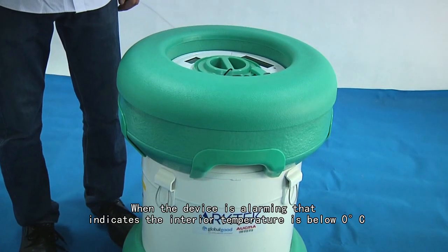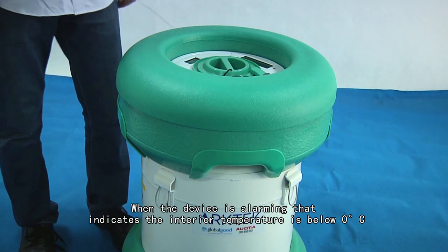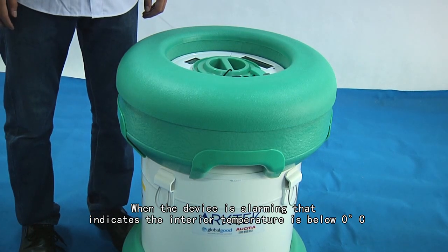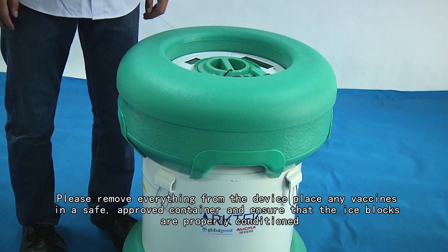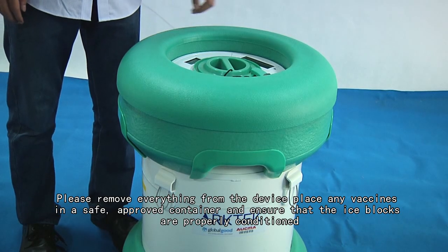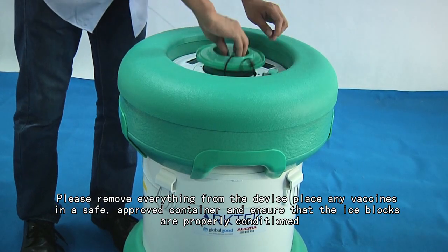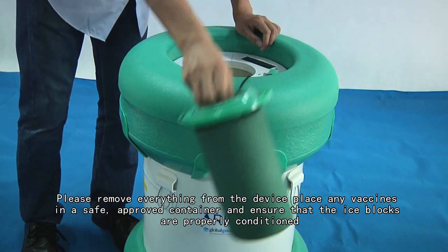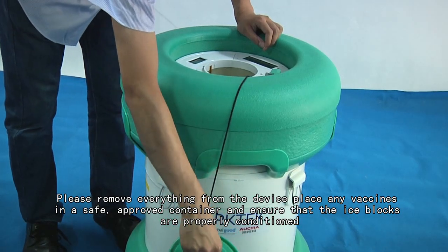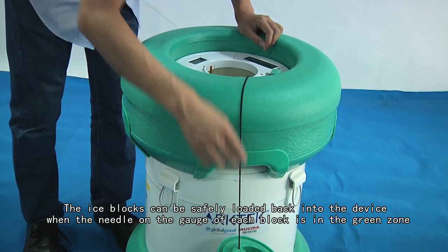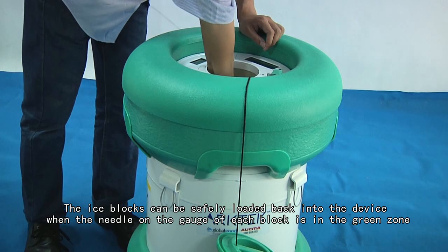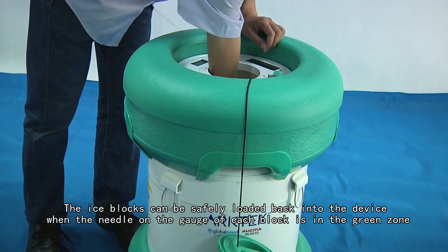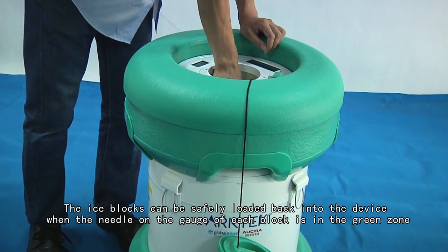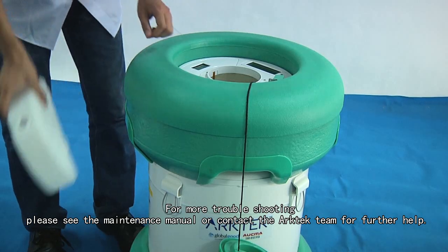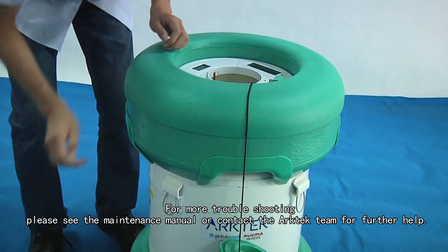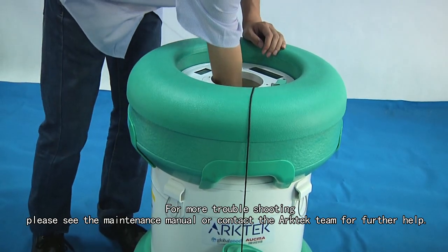When the device is alarming, that indicates the interior temperature is below 0 degrees, 2 degrees Celsius. Please remove everything from the device. Place any vaccines in a safe, approved container, and ensure that the ice blocks are properly conditioned. The ice blocks can then be safely loaded into the device when the needle on the gauge of each block is in the green zone. For more troubleshooting, please see the maintenance manual or contact the Arktek team for further help.